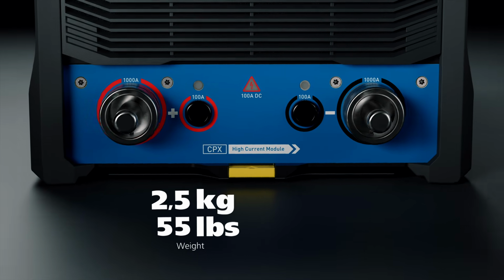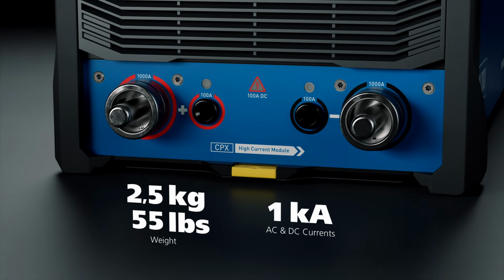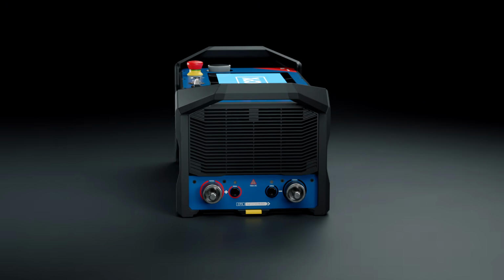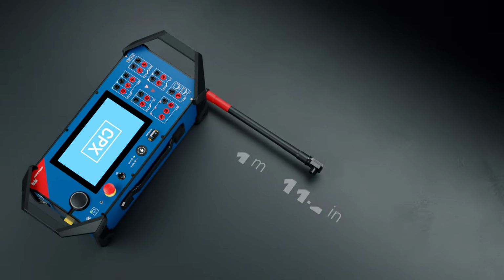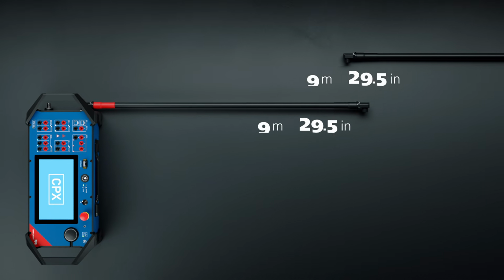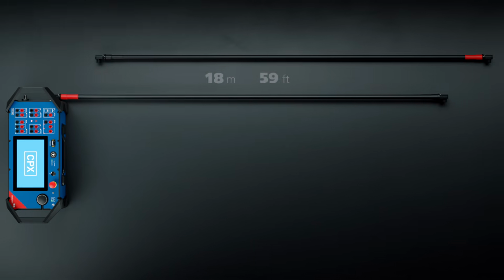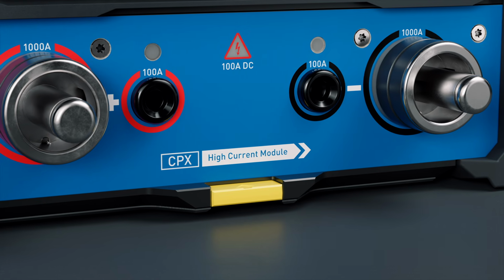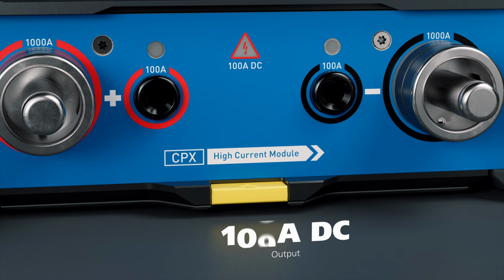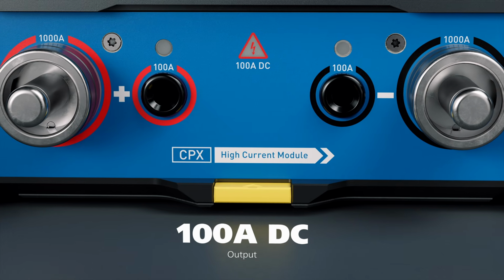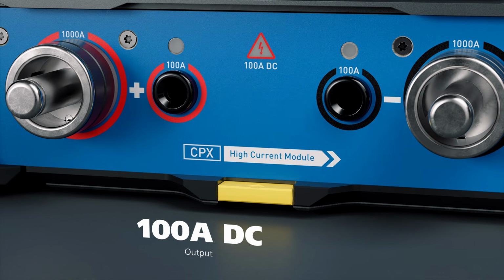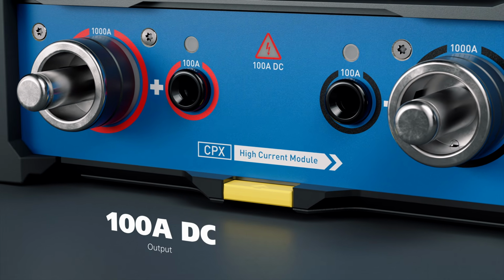One of these optional upgrades is the phenomenal high current module. This thing is a monster. It weighs just 2.5 kilograms, but generates high currents up to 1 kiloamp AC and DC. Thanks to the enormous power of 5 kVA, you can use cables up to 18 meters in length, giving you all the flexibility options you need to connect your asset. In addition, we have integrated a 100 amp DC output with an active discharge circuit. We did this to focus on power transformer tests. Even cables that are 50 meters long can be used here.